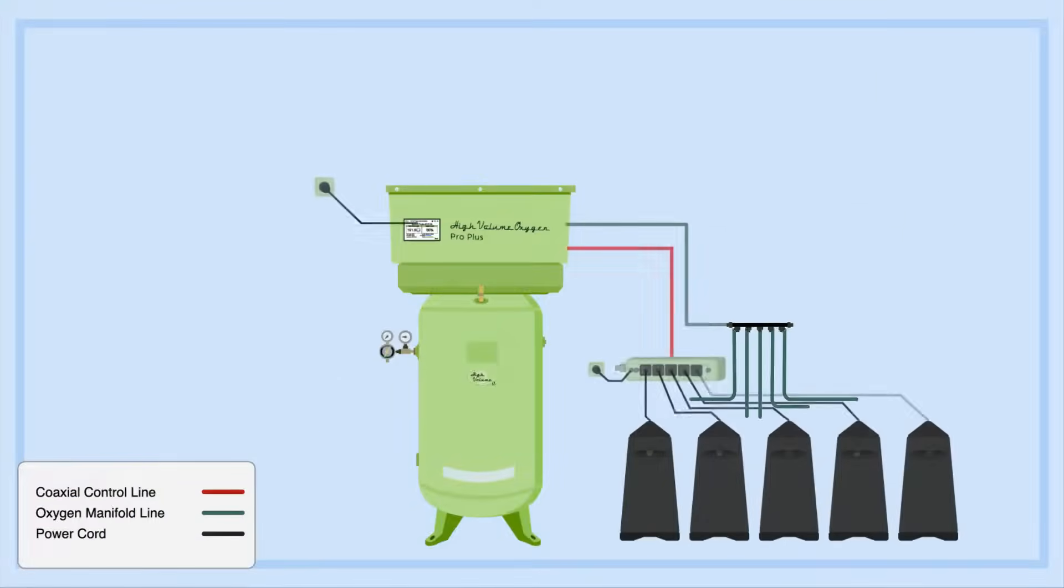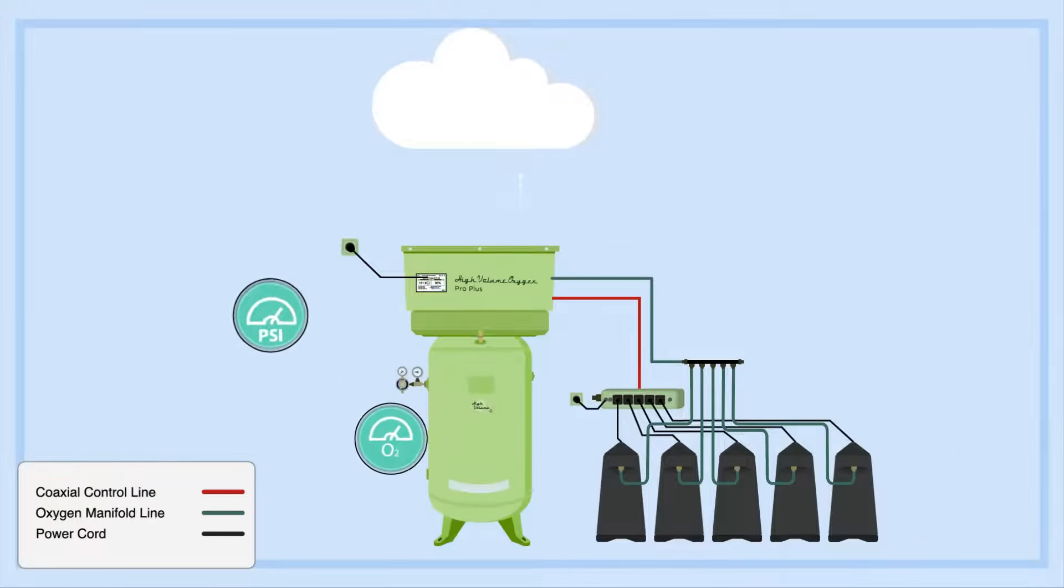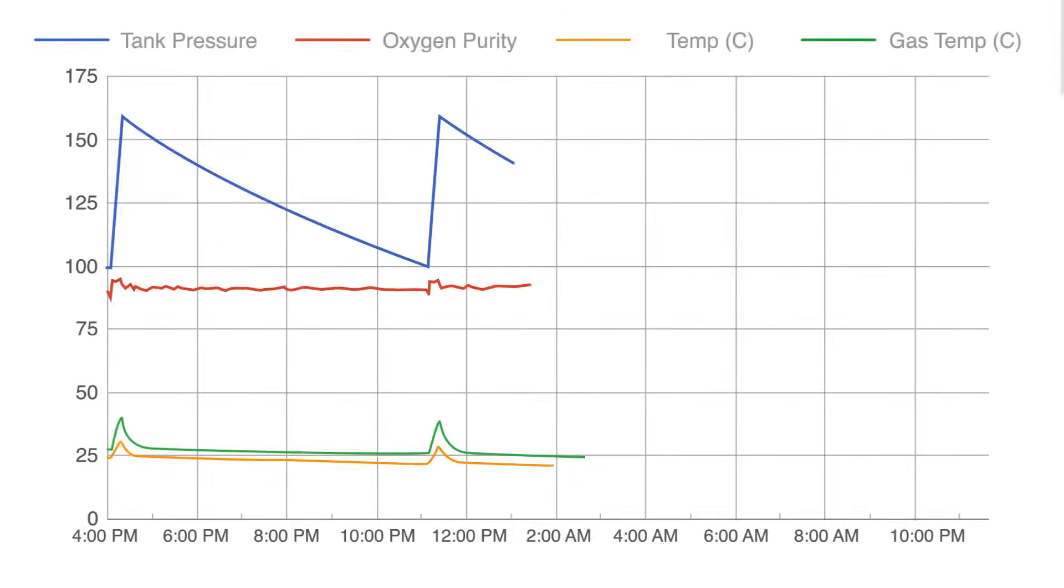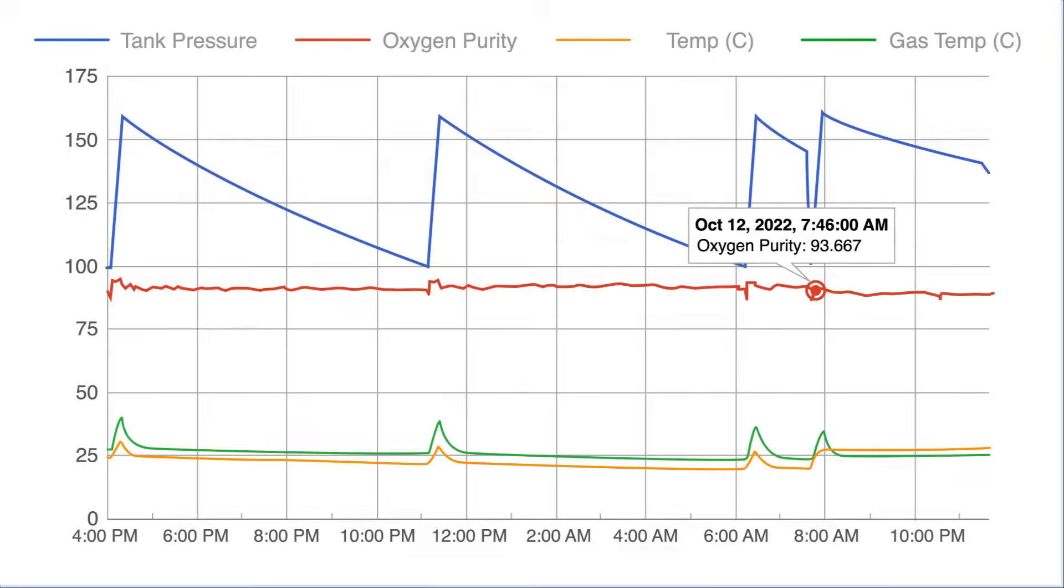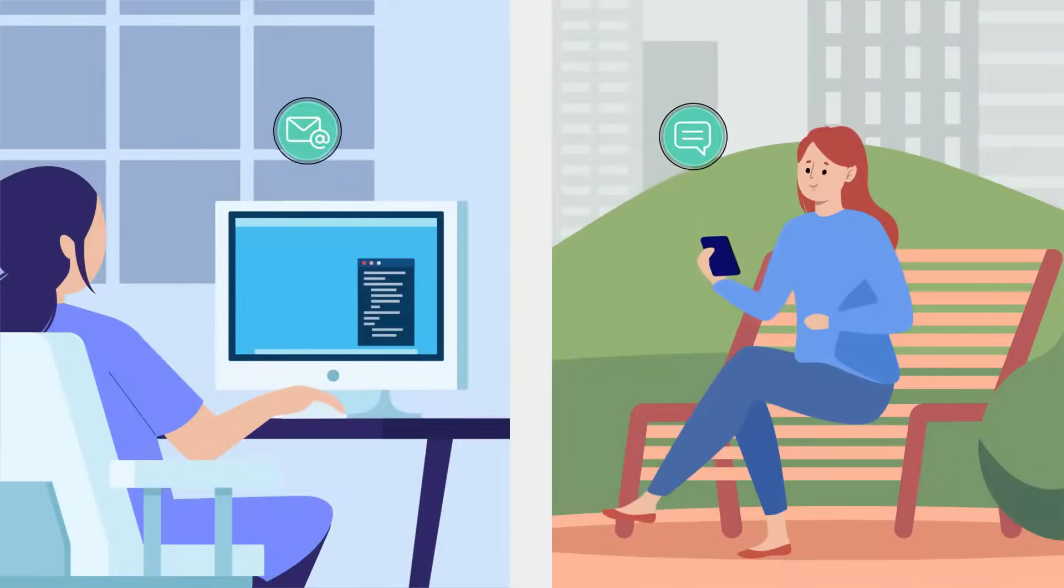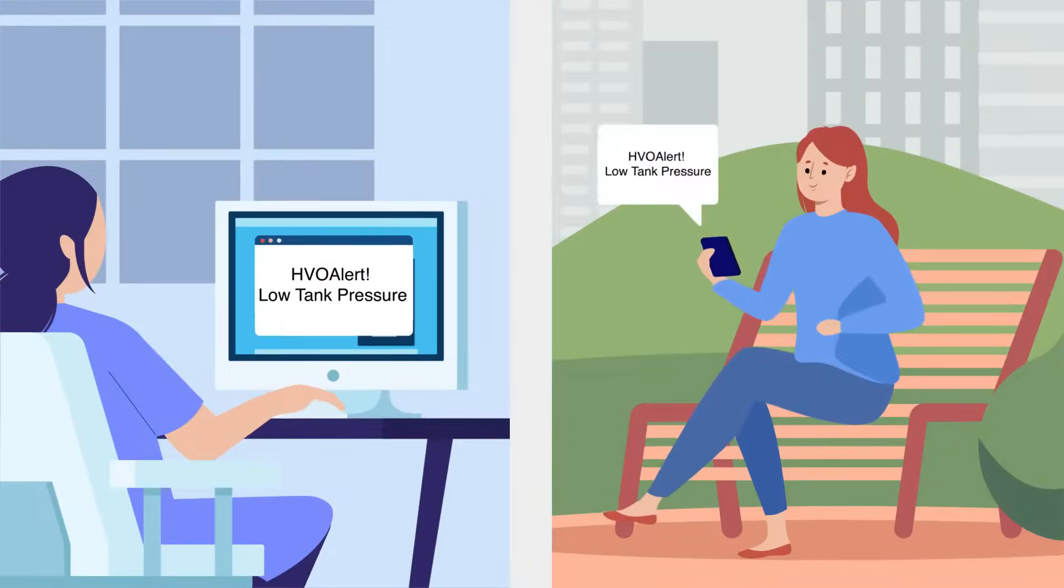Every HVO ProPlus system has built-in sensors that monitor tank pressure, oxygen percentage, enclosure temperature, and gas temperature, which it sends to the cloud every 10 seconds and can be viewed online. When actionable conditions are discovered, notifications are sent via email and text message.